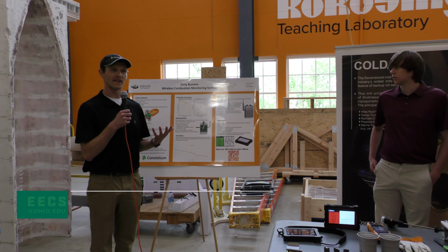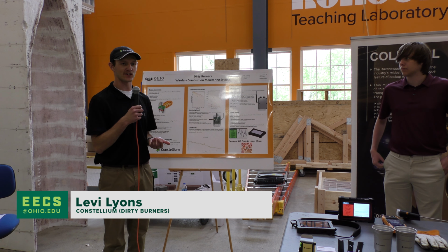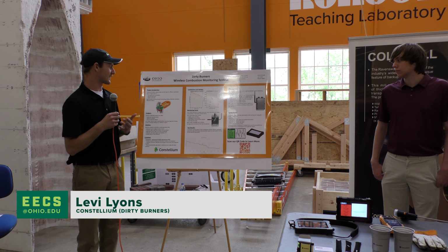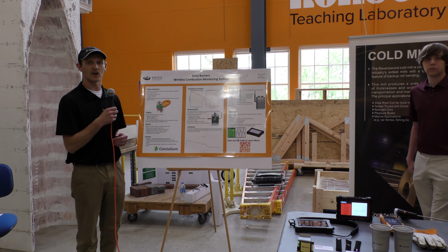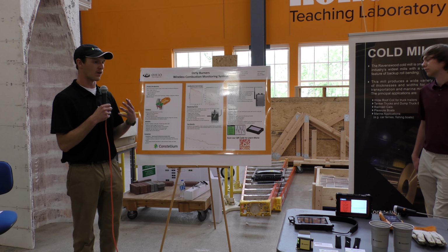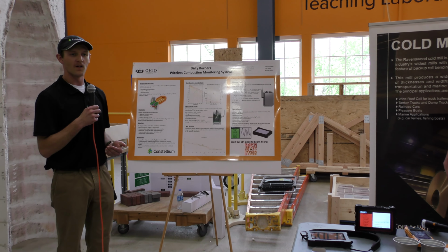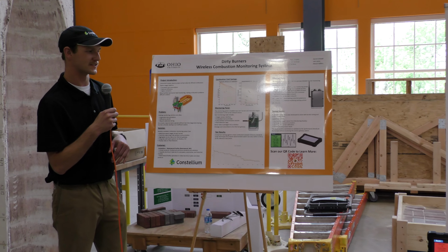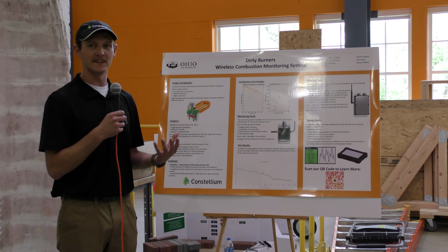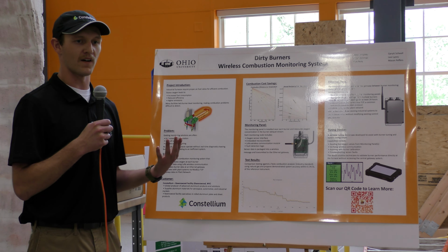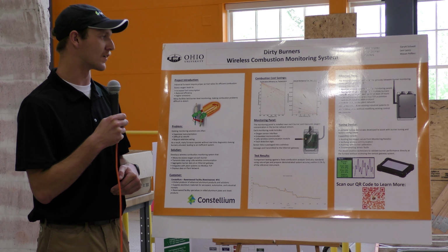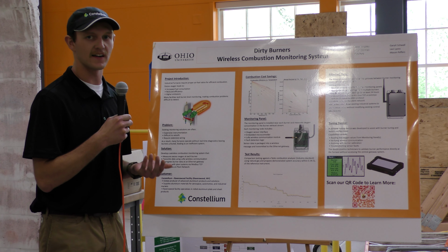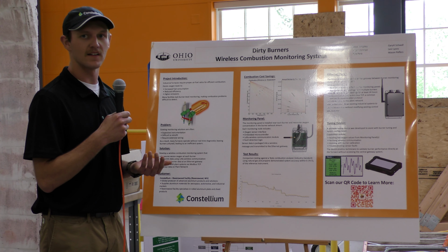You may ask why you care about excess oxygen. Basically, that's a main constituent in the combustion process, in any combustion process, in a car engine or a wood stove or propane or any natural gas combustion system. What you put in is air and fuel, and you get out CO2 and heat and a little bit of air that's left over. So what we're monitoring is excess air, because that's very determinant in the efficiency of the entire system.